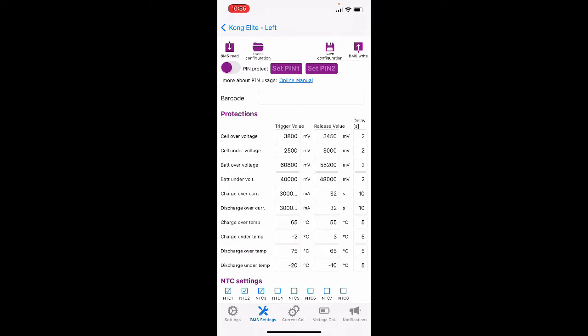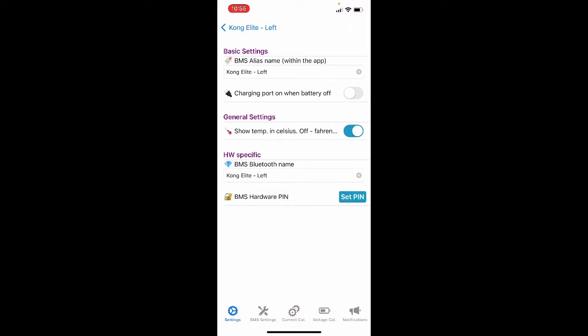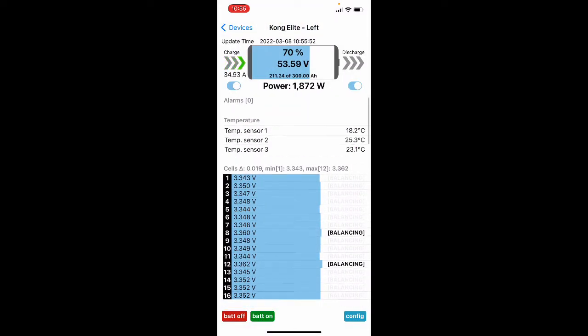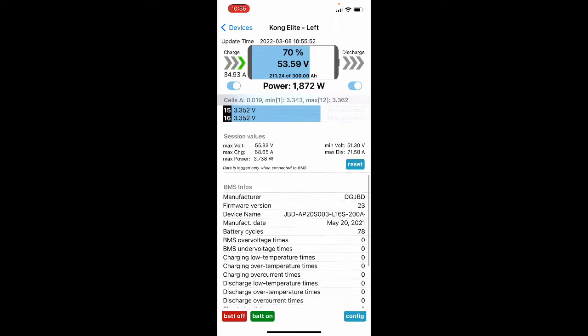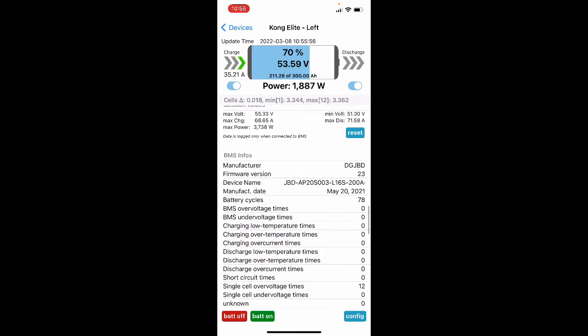By lowering the float voltage setting, my hope is that I'll stop these cell over voltage events from occurring. Of course, it would be good if the BMS did its job and prevented that one cell from hitting 3.8. The other cells are around 3.6 when this occurs, so it's really a bad thing happening on the BMS's part - it's not doing a great job of keeping them in check.